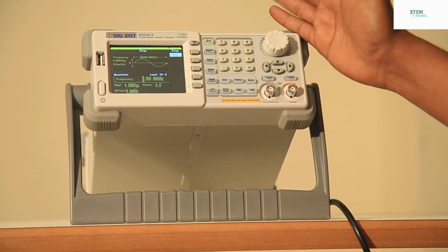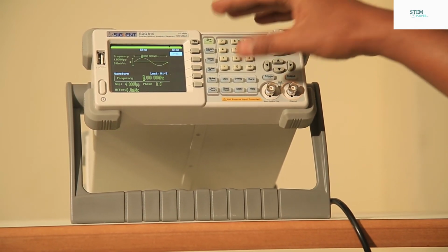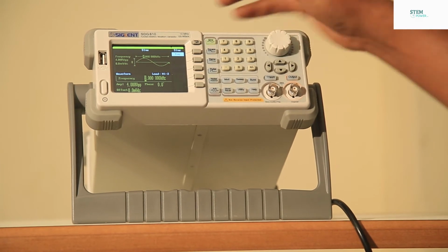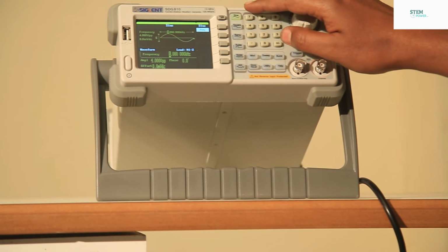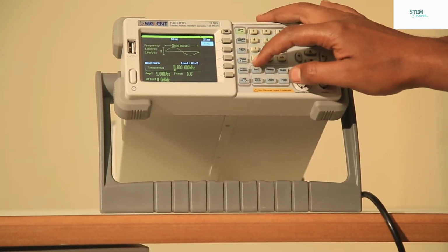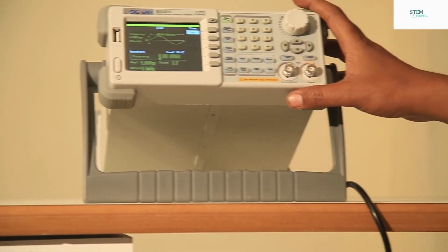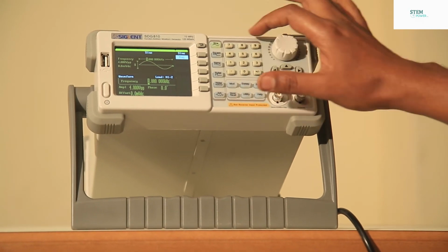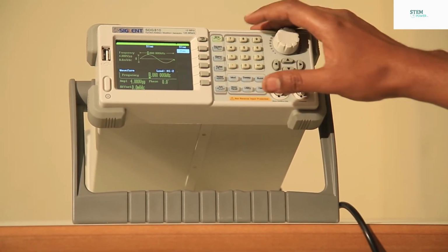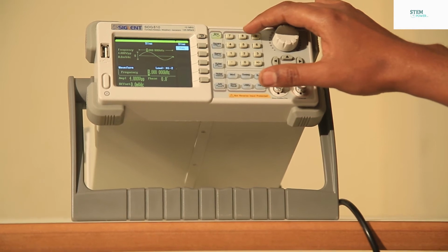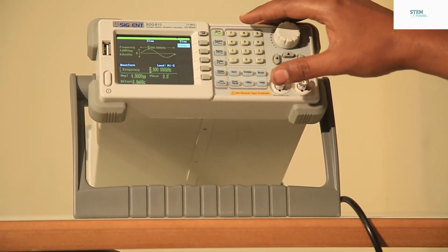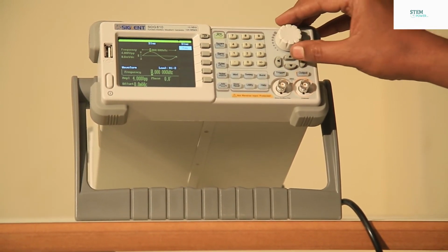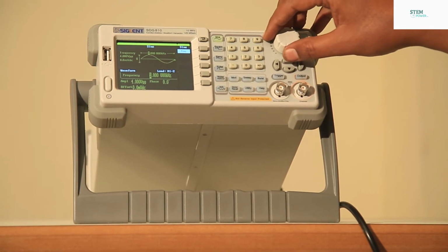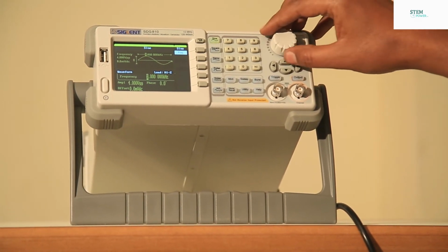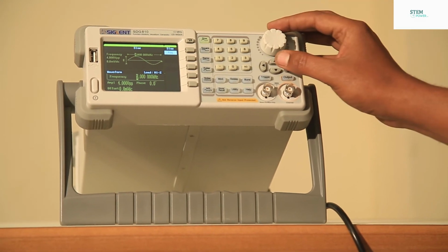This equipment produces and delivers different types of electrical signal waveforms, like sine wave, square wave, ramp wave, pulse wave, noise, and arbitrary. There is a numeric keypad here, so to set a parameter you can use the keys or the knob. Turning clockwise increases the value, anti-clockwise decreases it.